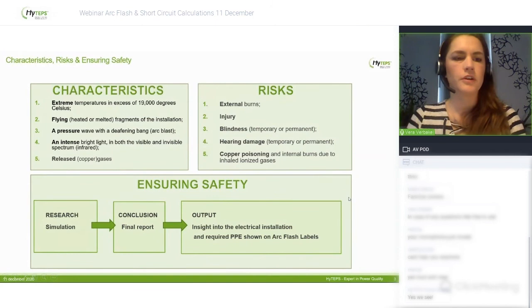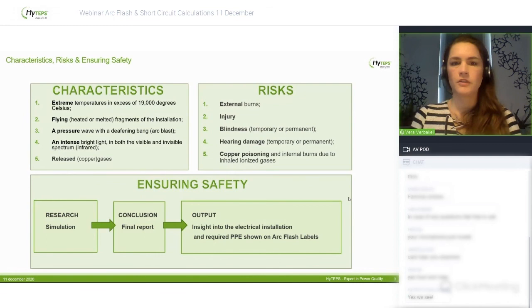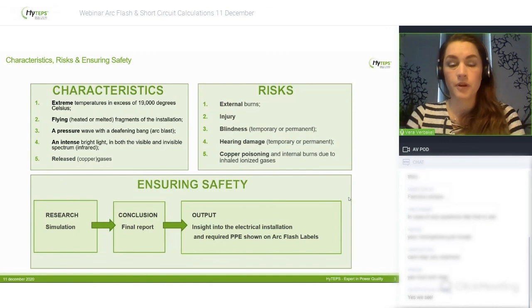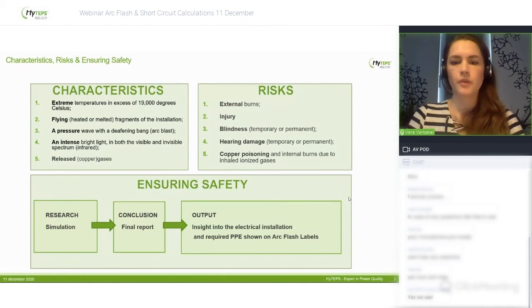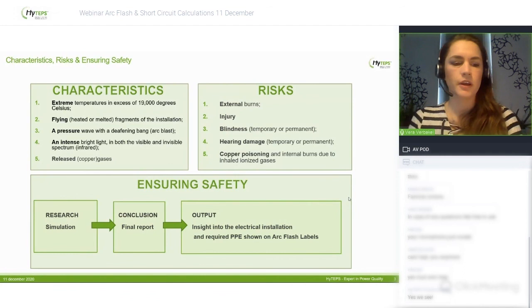The characteristics of an arc are extreme temperatures above 19,000 degrees Celsius, flying fragments of the installation — heated or melted parts — a big pressure wave with a deafening bang, and an intense bright light with both visible and invisible spectrum, as well as released copper gases. The risks are significant: you can get external burns, injury, temporary or permanent blindness or hearing damage, and also copper poisoning and internal burns due to inhaled ionized gases.